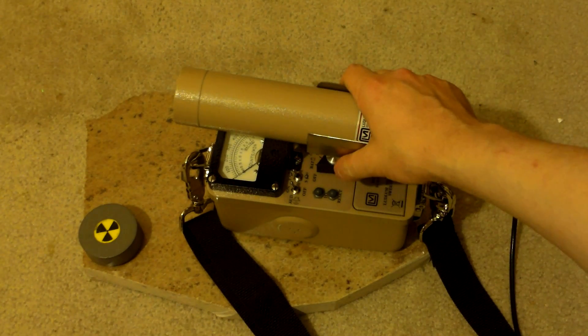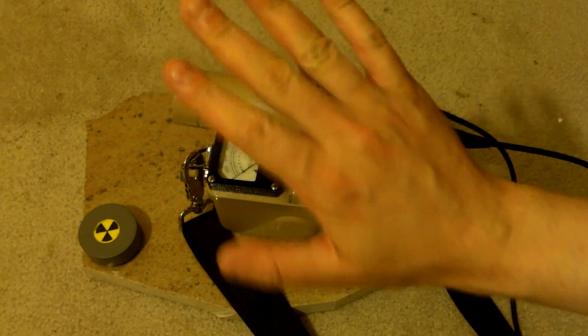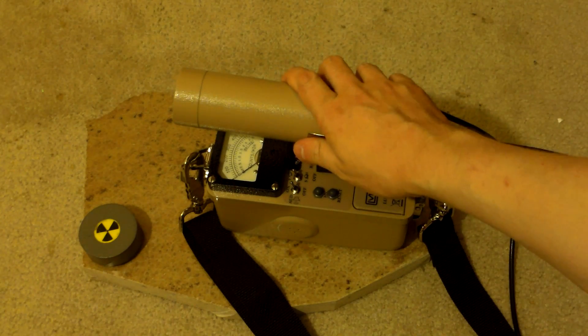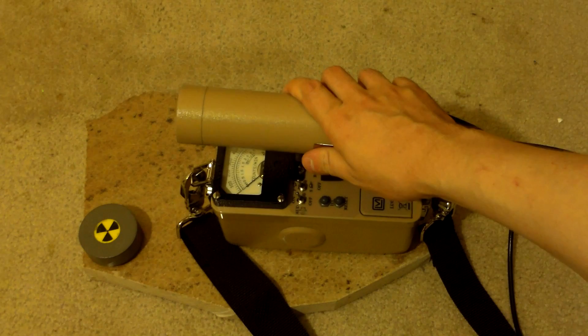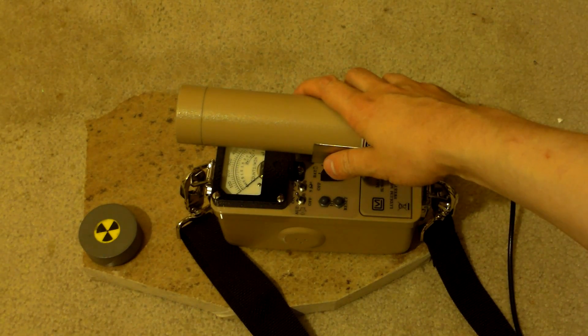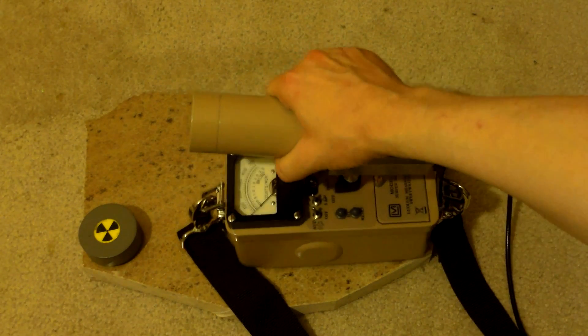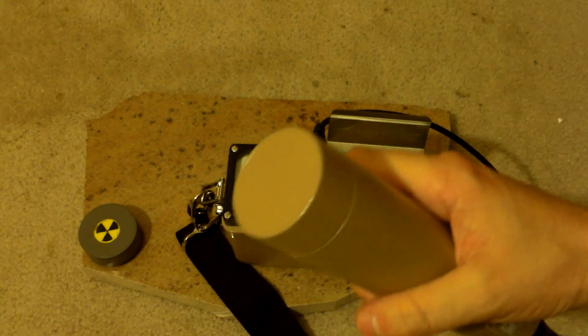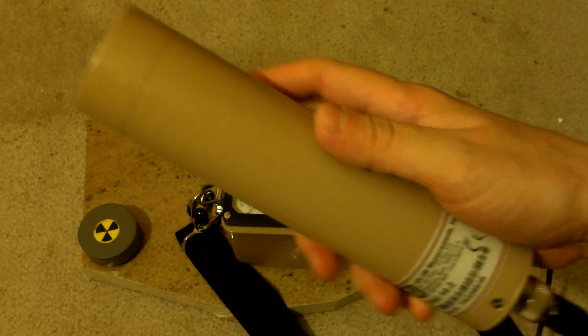This is a Ludlum Model 12 — not the Model 3, that's the less expensive one. This is the good one. The Model 3 is for Geiger counters for the most part; this one right here is built for scintillation detectors. It'll run a Geiger counter too, but it's really designed for scintillation, with a 1-inch sodium iodide thallium-doped scintillation probe which can be used for gamma spectroscopy.